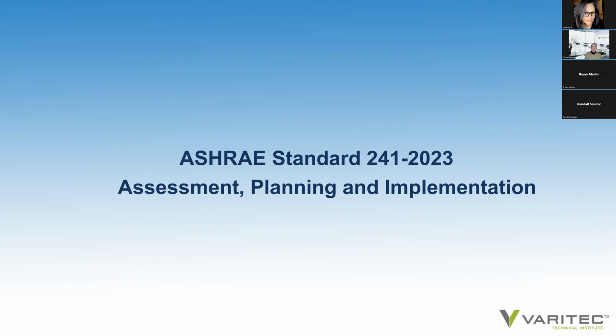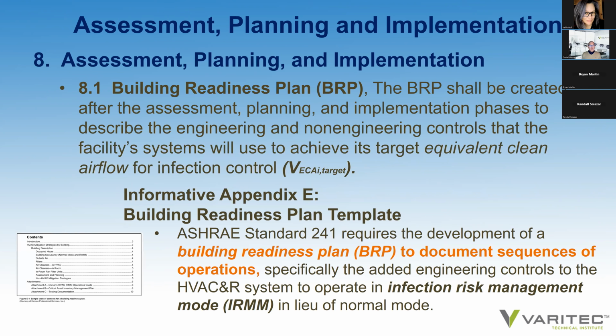other prescriptive measures Standard 241 offers. We're going to look at assessment, planning, and implementation. The standard calls for every building to have a building readiness plan that shall be created after the assessment, planning, and implementation phases to describe the engineering and non-engineering controls that the facility systems will use to achieve its target equivalent clean airflow. It provides a building readiness template, as shown in the table to the left, that documents the sequences of operations and the engineering controls that will go into operation to meet the infection risk management mode requirements.